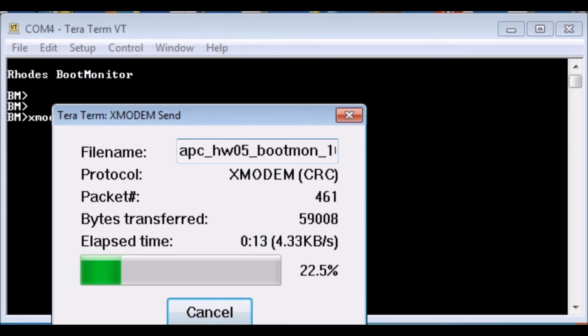Lastly, you'll want to do what's called the application module. The name of that file will depend upon the type of firmware for the UPS you're using. For smart UPSs, it will have SUMX. For a Symmetra single phase, it will have SY. For a Symmetra three-phase unit, it will have SY3P. And for a Rack ATS, it will have ATS4G.